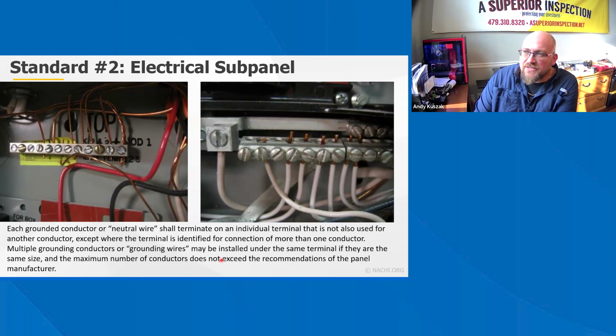The SER, which is the service entrance cable, is commonly used to supply electricity to subpanels. A typical subpanel is commonly supplied by a 100 amp feeder using number 2 aluminum or a number 4 copper cable. Number 3, the equipment grounding bar must be bonded to the subpanel enclosure, and a bonding jumper to the neutral bar must not be installed. And then 5, lastly, a main breaker is not required for the subpanel if overcurrent protection is provided for the feeder conductors.